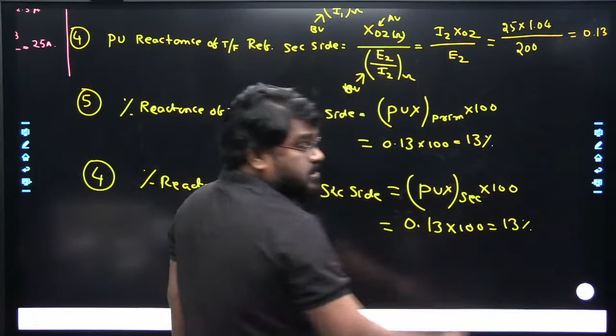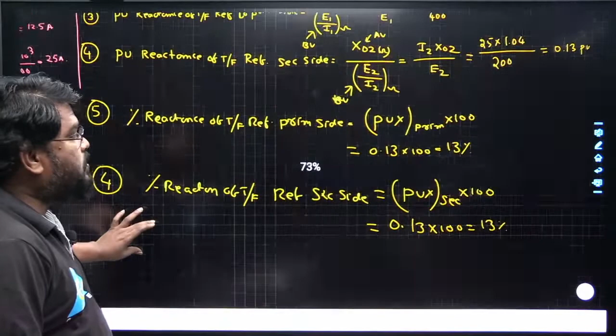The fourth one is the per unit reactance of the transformer referred to the secondary side. First, how do we get the formula? Here, referred to the secondary side, total reactance referred to the secondary side is X02, in ohms. That is the actual value divided by the secondary side base value, base voltage over base current on the secondary side, which is also in ohms. So actual value in ohms divided by base value in ohms. Got it?